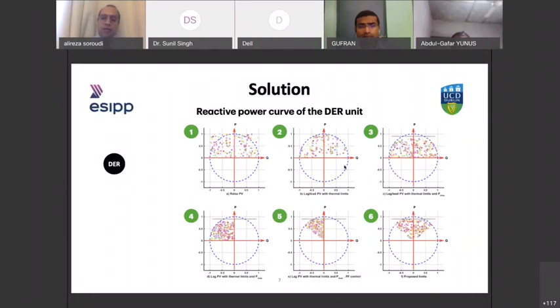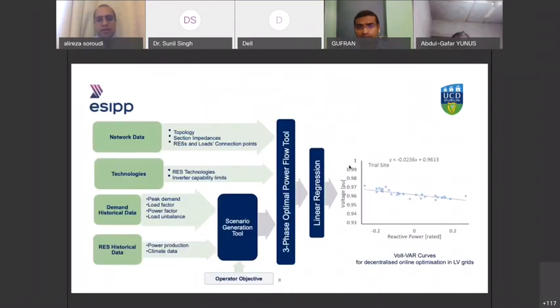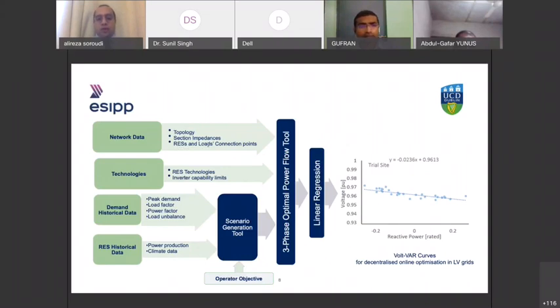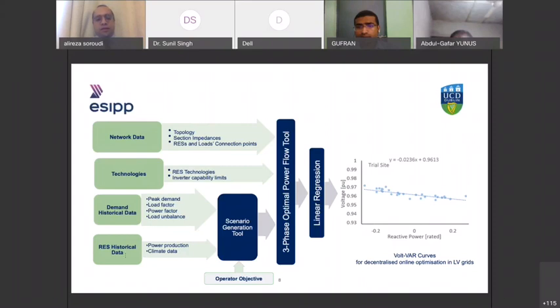There are different levels of data required: network topology, network impedances, how renewable energy resources are acting, the load, which phase they are connected to, the capabilities of the inverters, and the demand profile — including historic peak values, load factor, phase distribution, and historical data of renewable energy sources. We use them for scenario generation and give it to a three-phase optimal power flow.